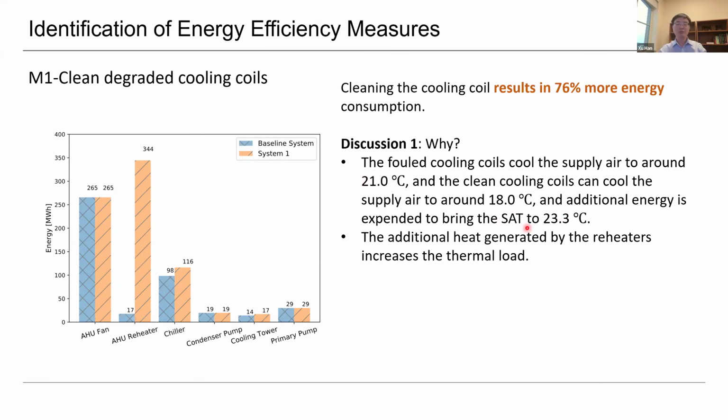We also propose other strategies to avoid this kind of simultaneous heating and cooling, right? They cool the air, and they also reheat the air. We want to try to minimize this. And also the additional heat generated by the heater increases the thermal load.